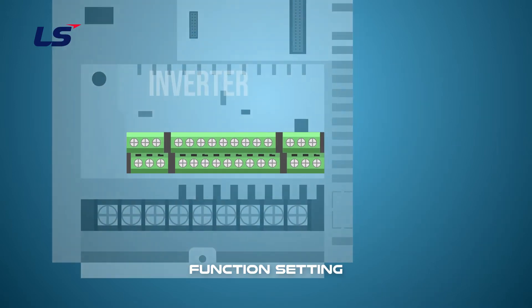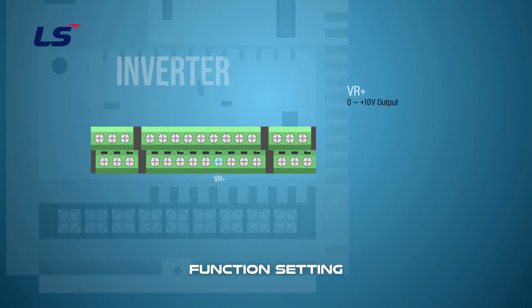The analog input-related terminals are VR plus, VR minus, V1, I1, and 5G. VR plus terminal is 0 to plus 10 volts, and V1 terminal is analog voltage input terminals. I1 is analog current input terminal, and 5G is for common terminal of analog input.